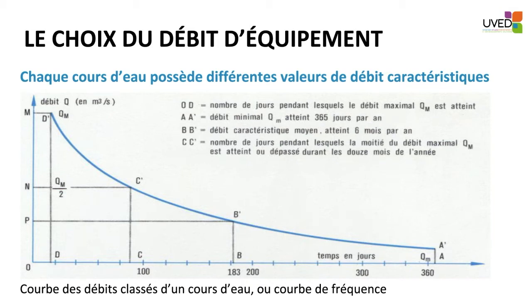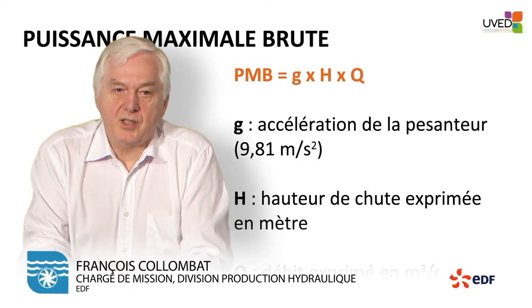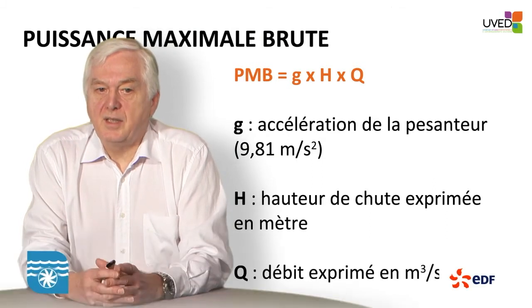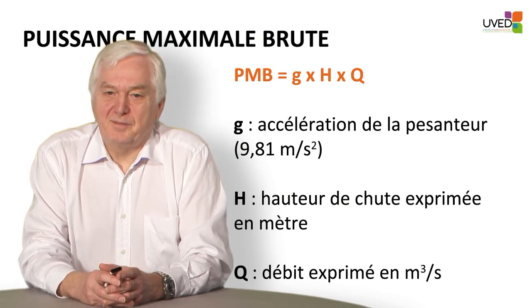Before the power plant is designed, it is necessary to define the best technical-economic value. The flow we are interested in is the average annual flow — BB prime — the characteristic average flow six months per year. If we have this type of flow six months a year, this will be the figure we rely on to design the power plant. Once the head H has been determined as well as the flow Q, it is relatively easy to proceed.